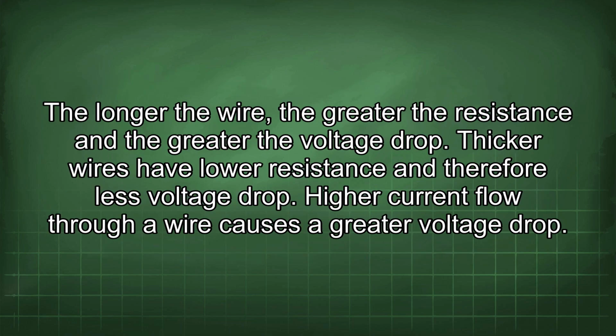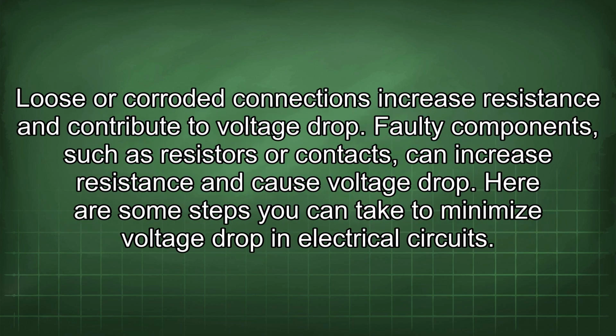The longer the wire, the greater the resistance and the greater the voltage drop. Thicker wires have lower resistance and therefore less voltage drop. Higher current flow through a wire causes a greater voltage drop. Loose or corroded connections increase resistance and contribute to voltage drop. Faulty components, such as resistors or contacts, can increase resistance and cause voltage drop.